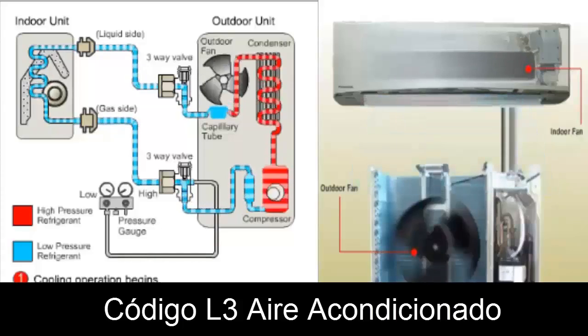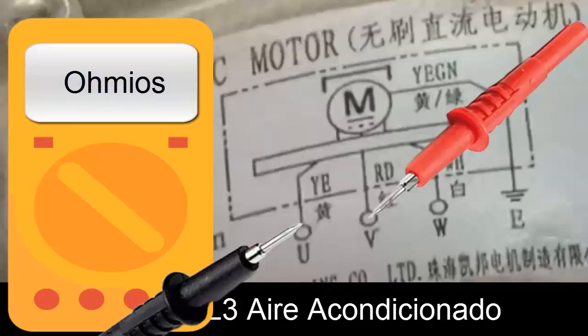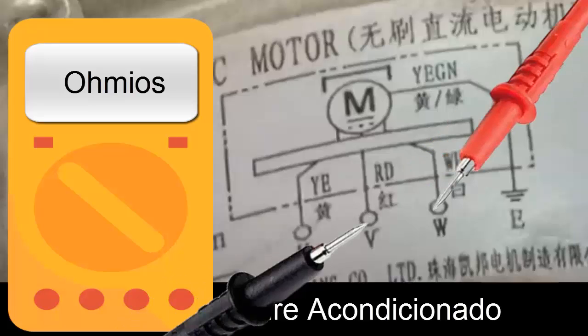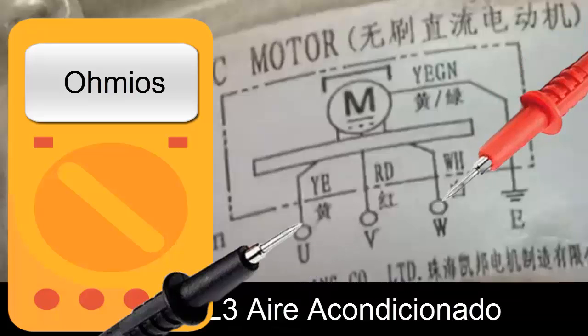4. Measure the fan's resistance. Disconnect the fan from the external electronic board. Use a multimeter on the resistance scale to measure the resistance between the fan wires. The values should be nearly equal. If not, replace the fan.